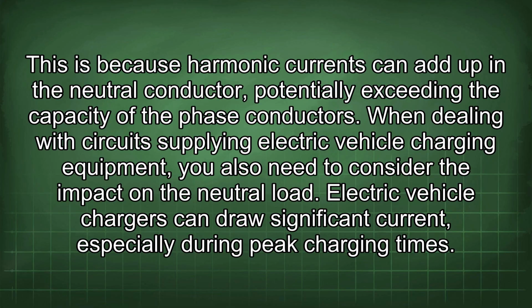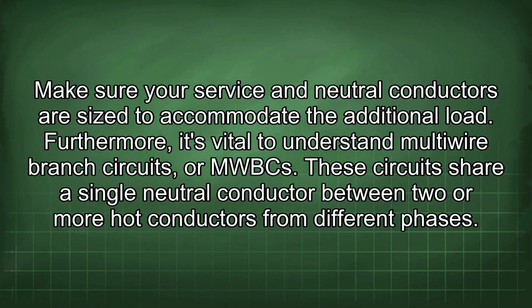When dealing with circuits supplying electric vehicle charging equipment, you also need to consider the impact on the neutral load. Electric vehicle chargers can draw significant current, especially during peak charging times. Make sure your service and neutral conductors are sized to accommodate the additional load.